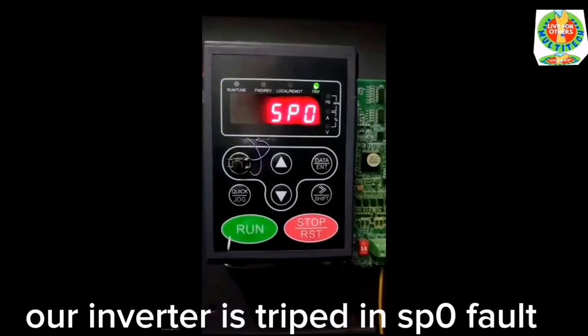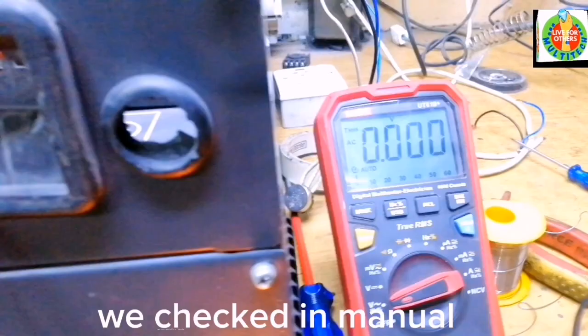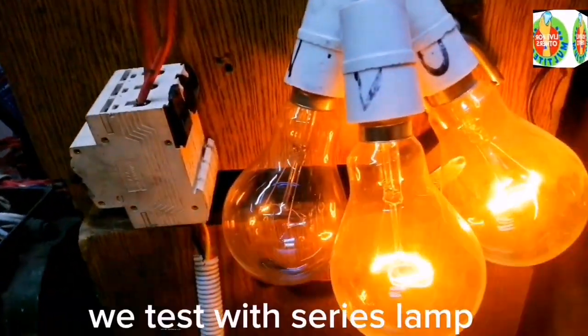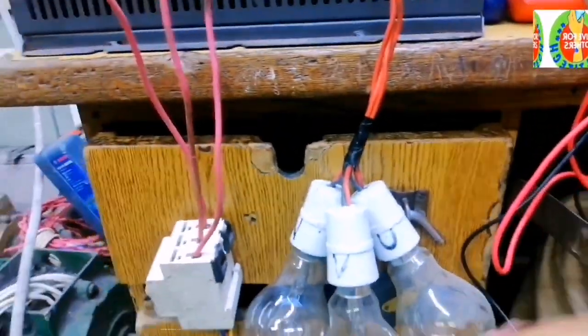Our inverter tripped with an SP0 fault. We checked the manual and found that it is a phase lost fault. We tested with a series lamp and confirmed that one phase is lost.